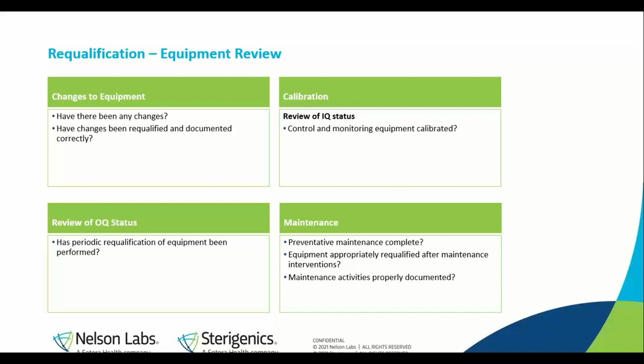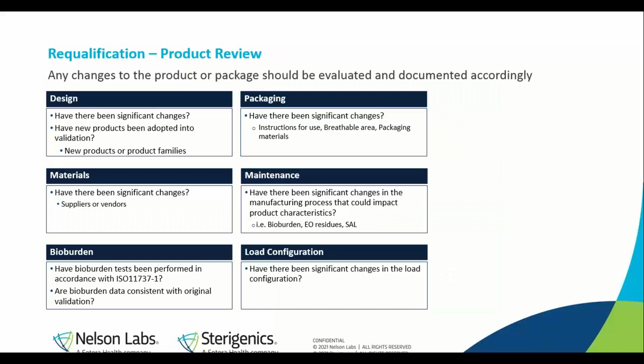Lastly, for the equipment review, you would want to evaluate any maintenance performed, whether it's preventative or due to a specific event. Was the equipment appropriately requalified after any maintenance intervention, and has that maintenance been properly documented? Once again, this is a great opportunity to work with a contract sterilizer to attain this information because they would have work instructions or procedures in place in order to evaluate the equipment on an annual basis. The next phase of the annual requalification review would involve the product. Any changes to the product or package should be evaluated and documented accordingly.